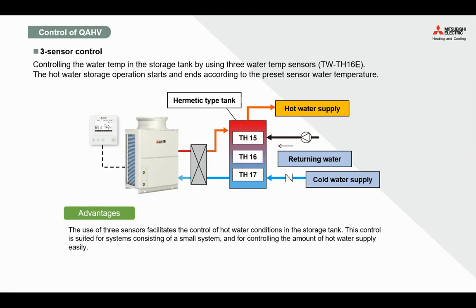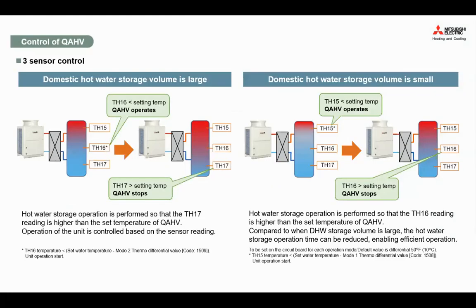So you can have TH15, 16, and 17, depending on what's required, and then turn on the unit depending on what's required on the 15, 16, and 17 to operate the unit to heat up the system. I mean, to heat up the water depending on requirement. So here, just as an example, if TH16 is lower than the set temperature, then the unit will start to heat up hot water. And when the bottom of your tank is getting hot, then the unit will stop, right?